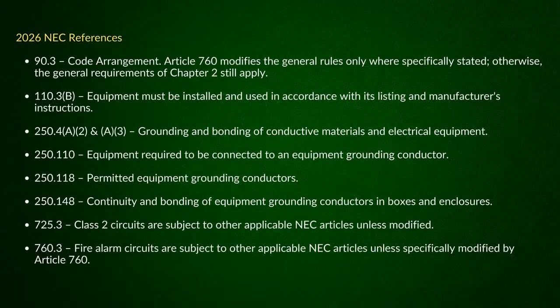Okay, yeah. Now the reason I referenced 250.110 and not 250.112, is because when you look at 250.112, you've got specific equipment fastened in place. True, and that's where you get into your switchgear and switchboard frames.